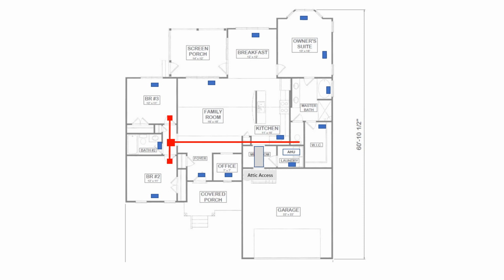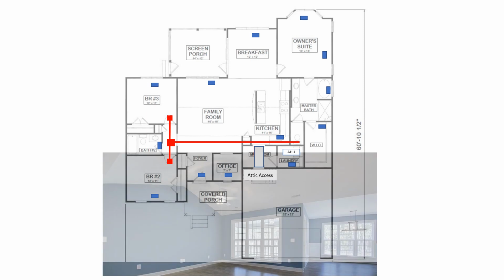I would just connect these small returns to the main return box, using it sort of like a plenum or a collection box. Then there was another problem, this time with the supply. Since the family room ceiling has a 14-foot peak and the roof deck was getting spray foamed, there would not be any great way to deliver air to this supply register. This would have to move to the other side of the family room, which would present a challenge delivering conditioned air to the opposite side of the room.